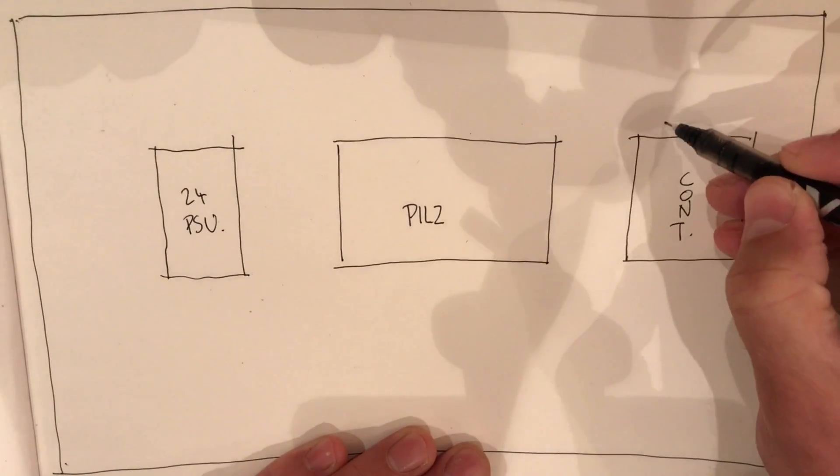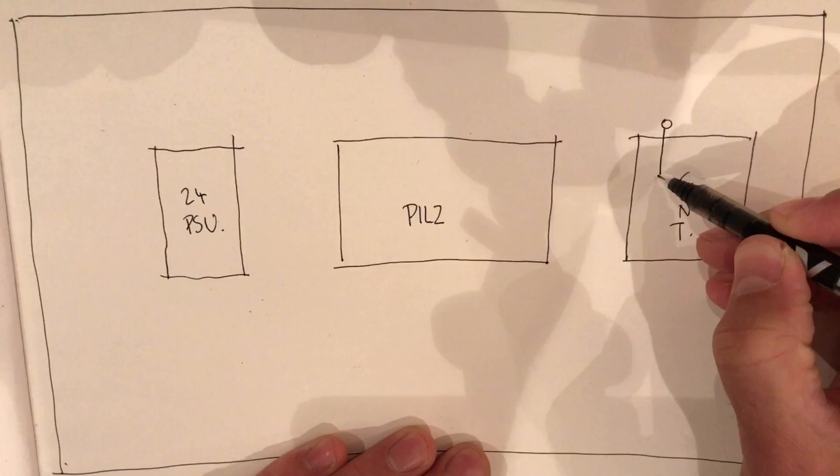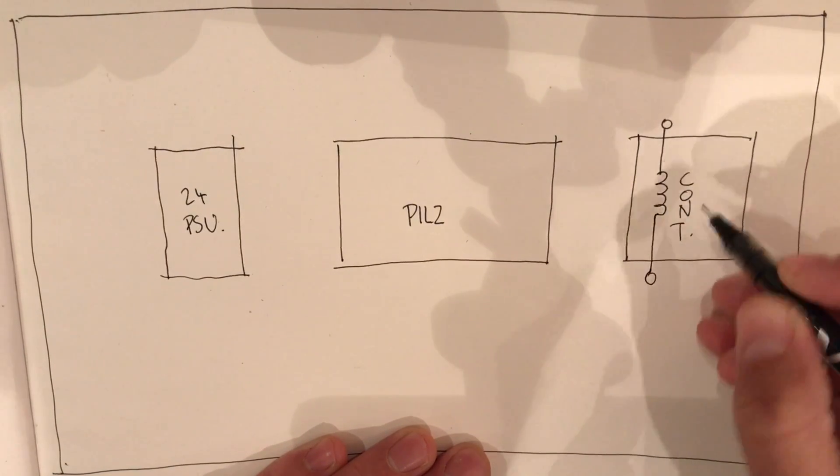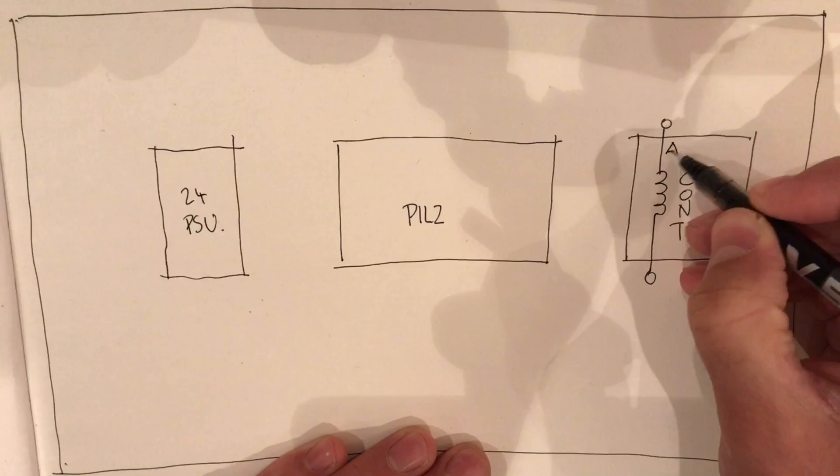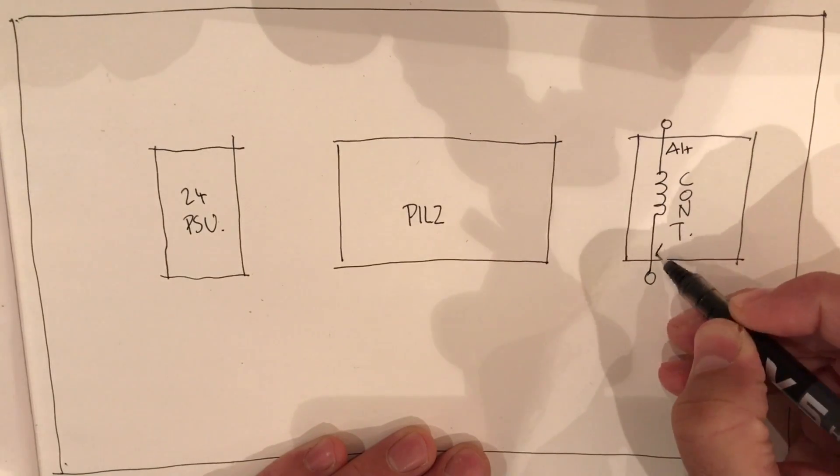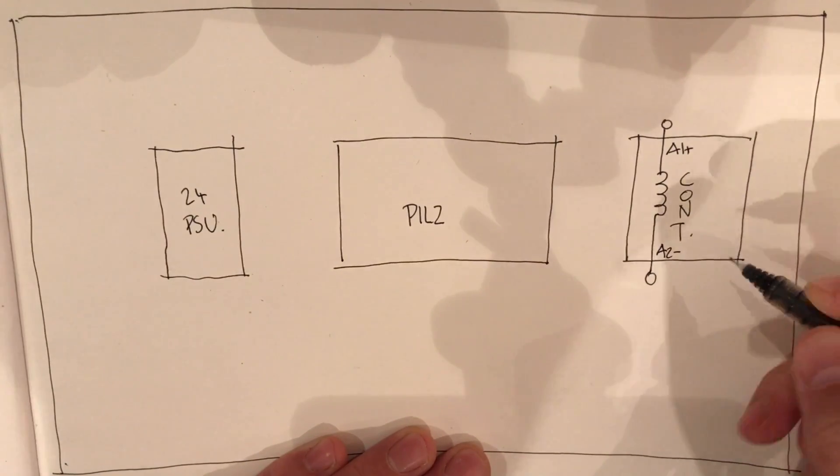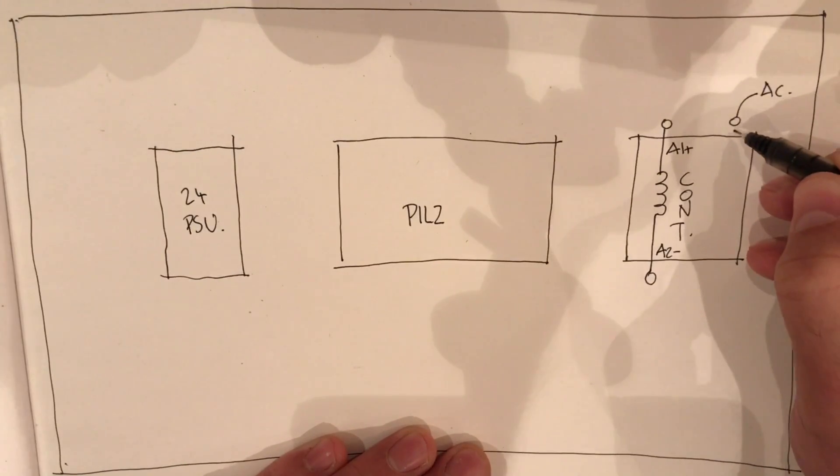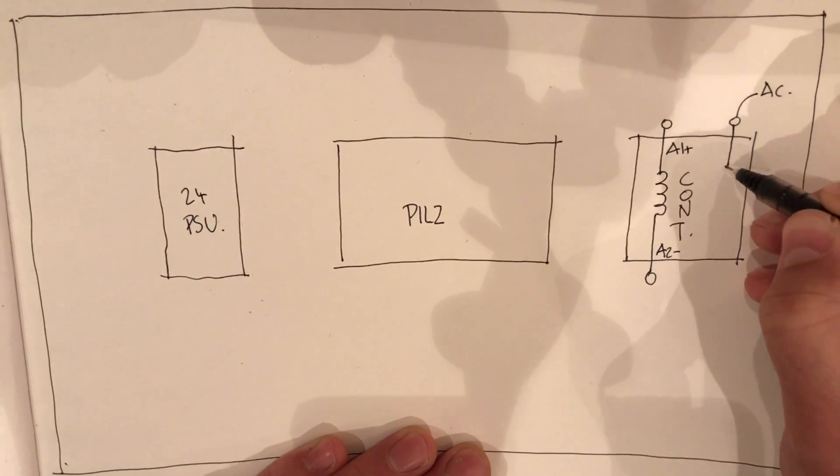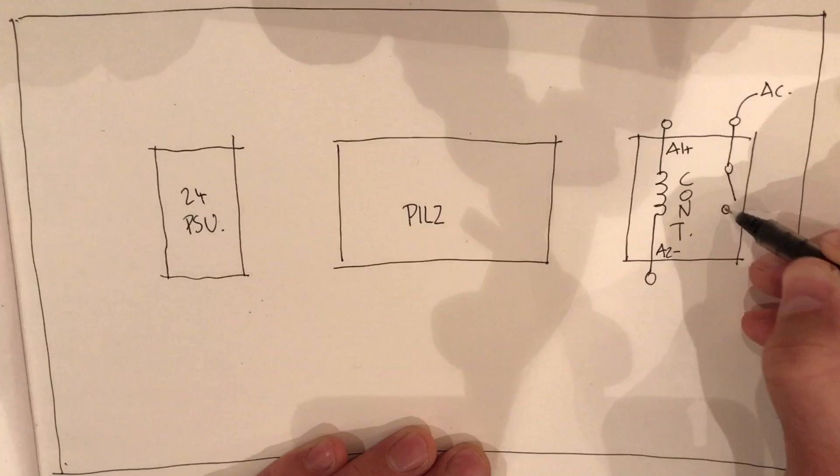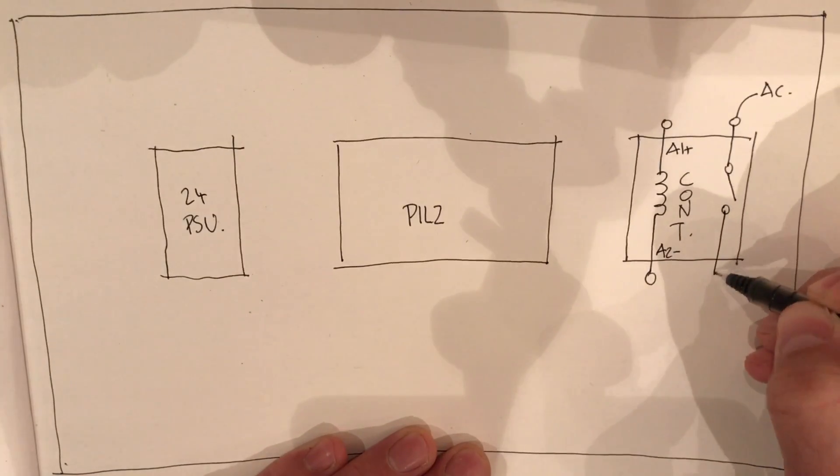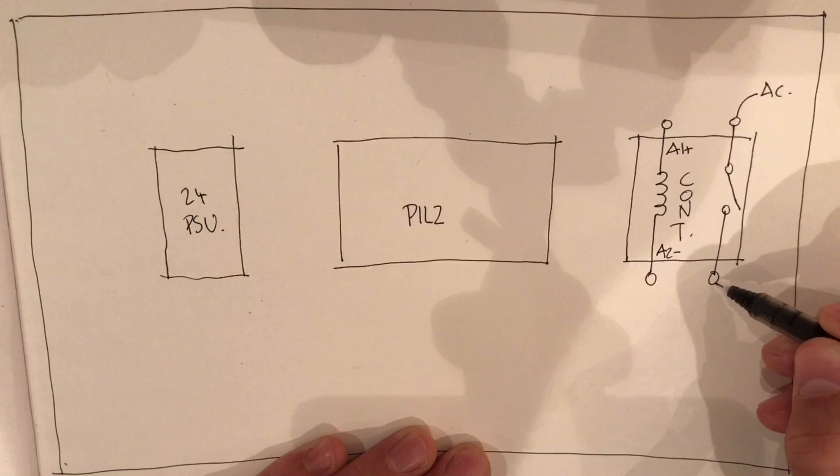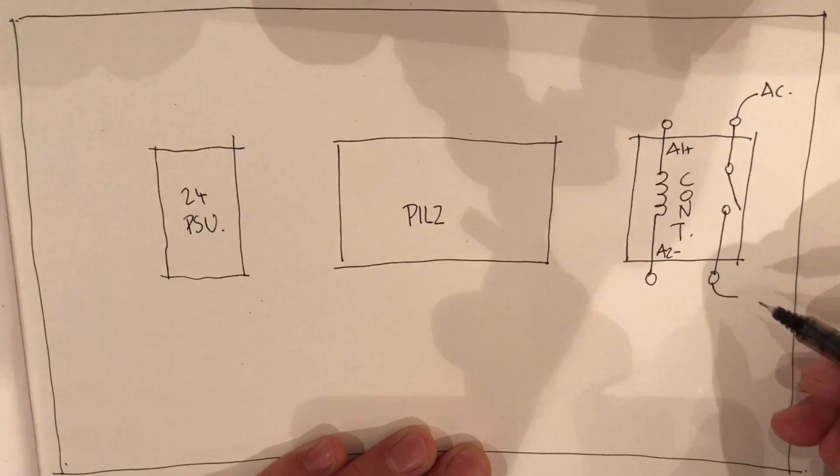The contactor has its main coil - A1 positive and A2 negative - and then you've got AC with its switch. When the coil's energized, the switch closes and the AC current flows.